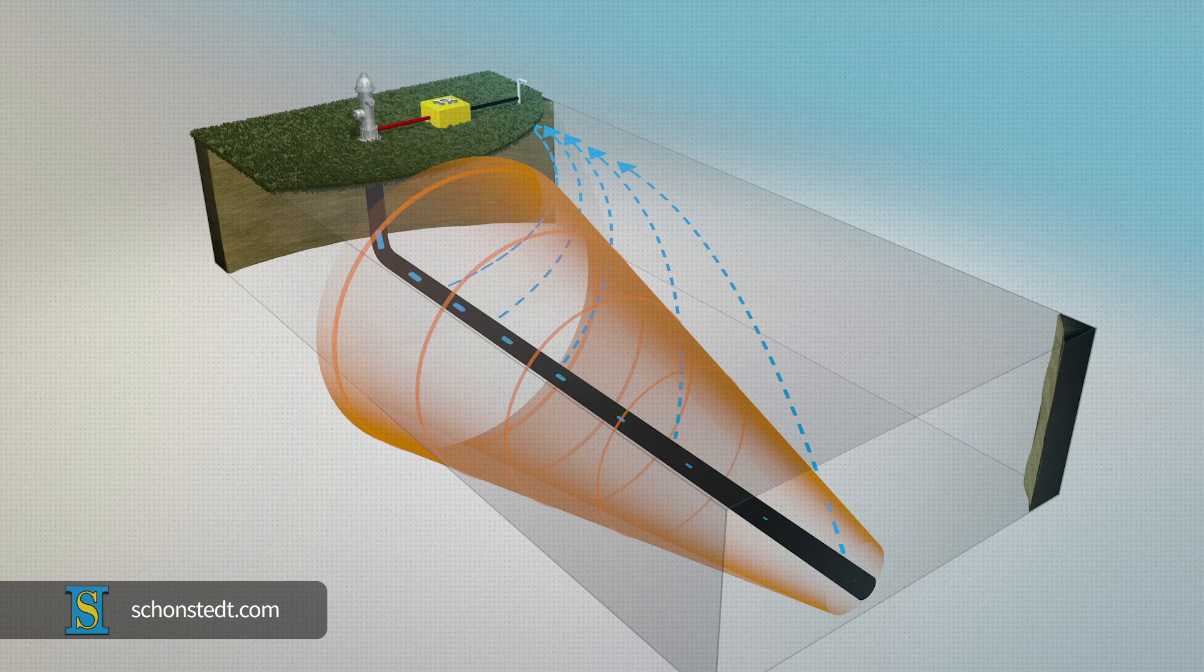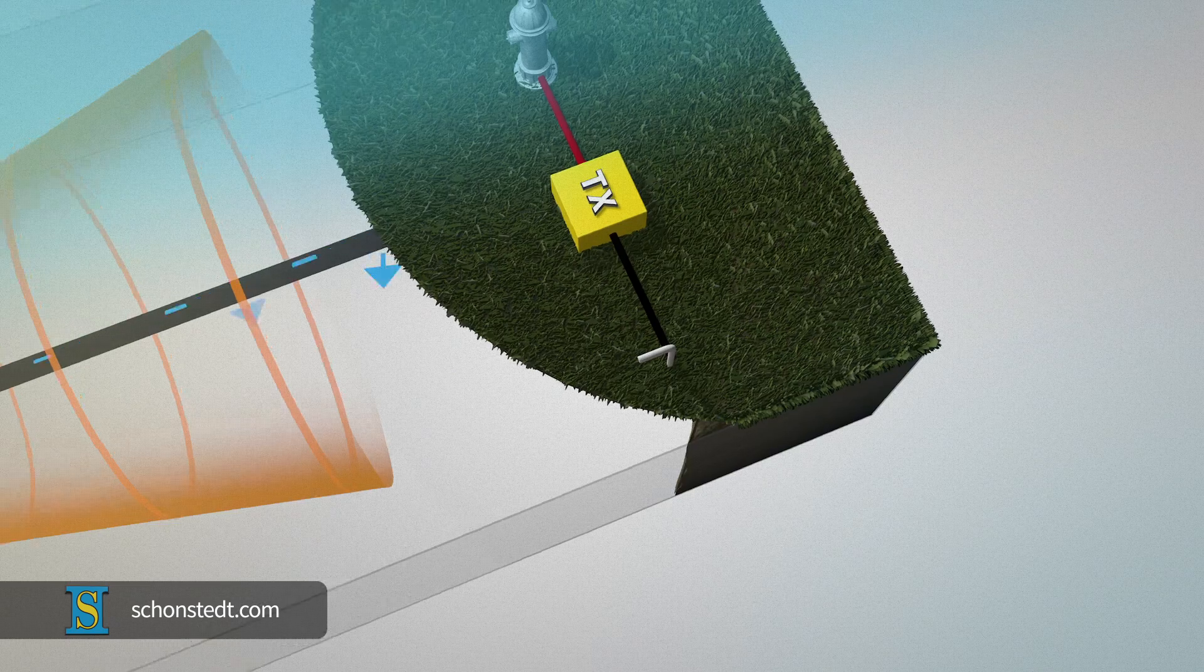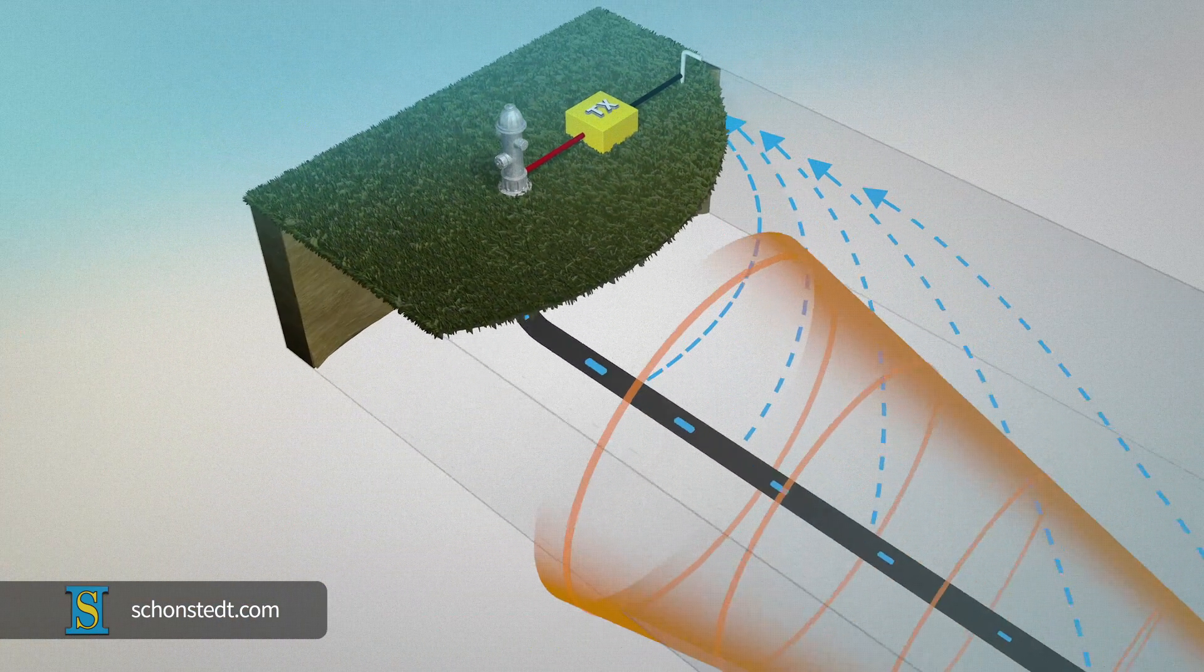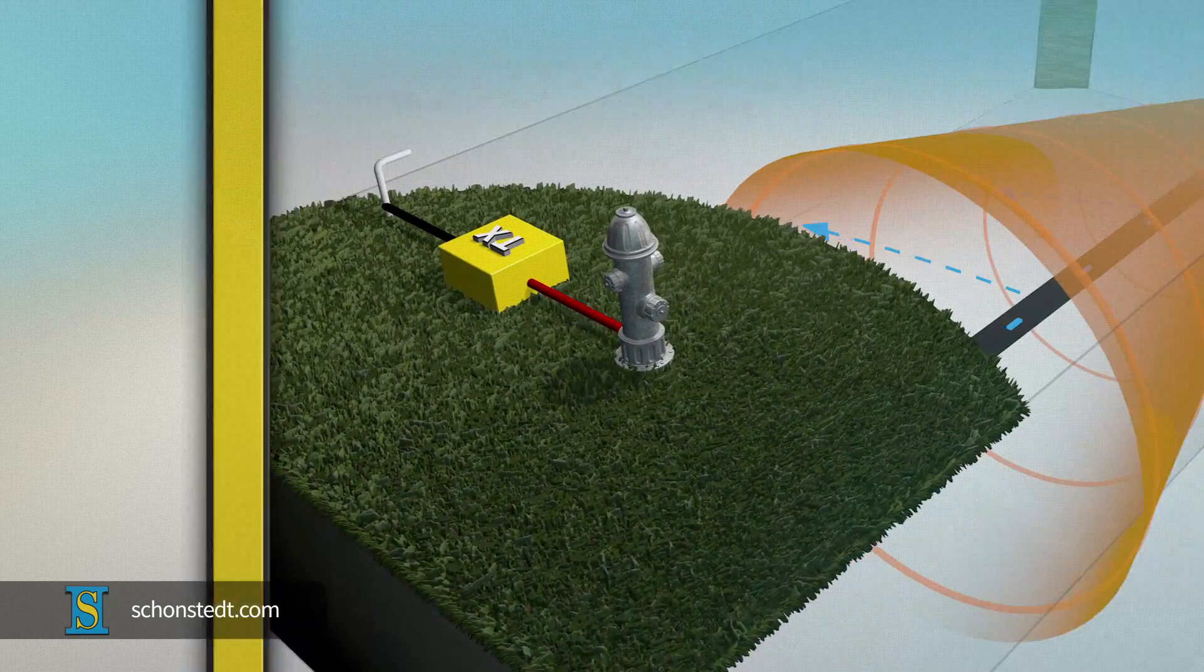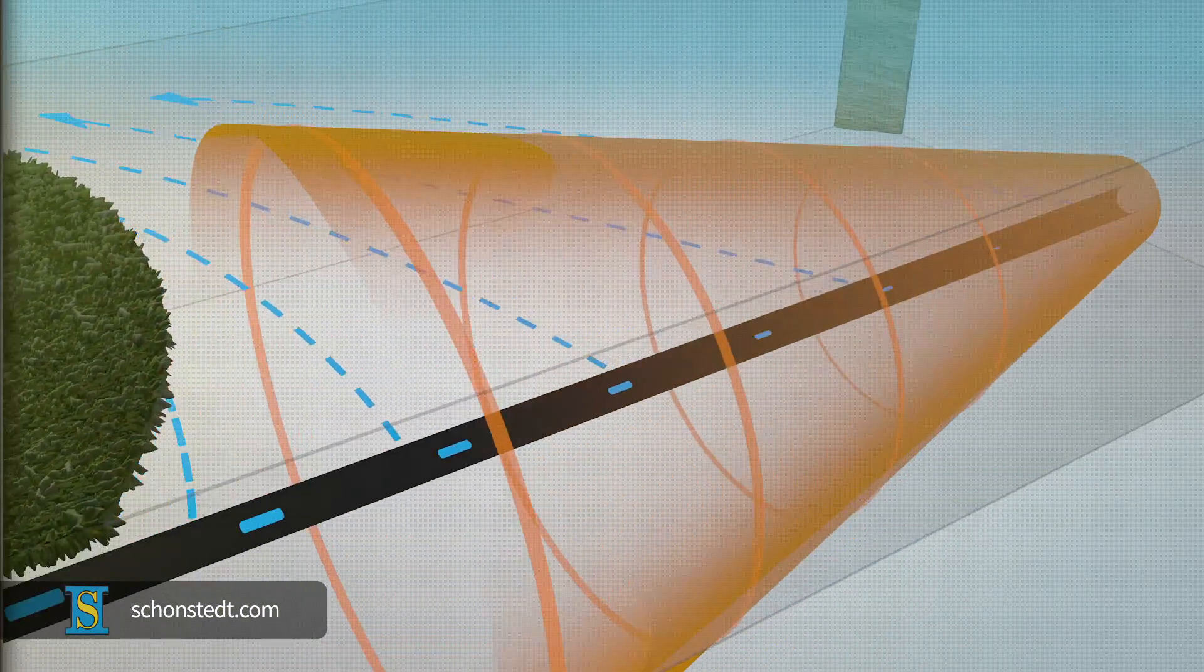In general, the better the ground, the better the signal. A current will now travel along the pipe or cable. As the signal travels, it gradually leaks into the ground and diminishes the farther it gets from the transmitter.